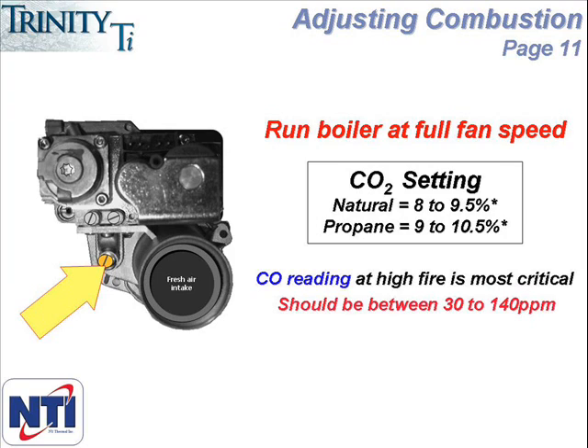The input screw is a multiple-turn needle valve — it is about 17 complete revolutions to go from fully closed to fully open and vice versa. When the screw is loosened, it allows more gas to pass through the valve. When it is tightened, less gas passes through.